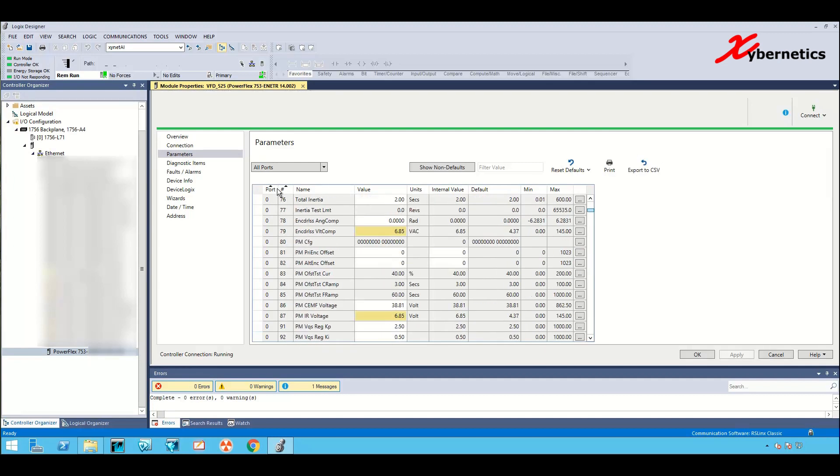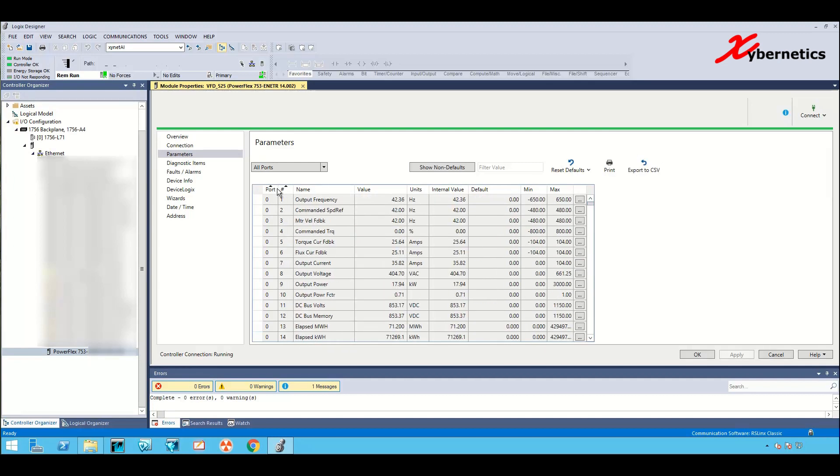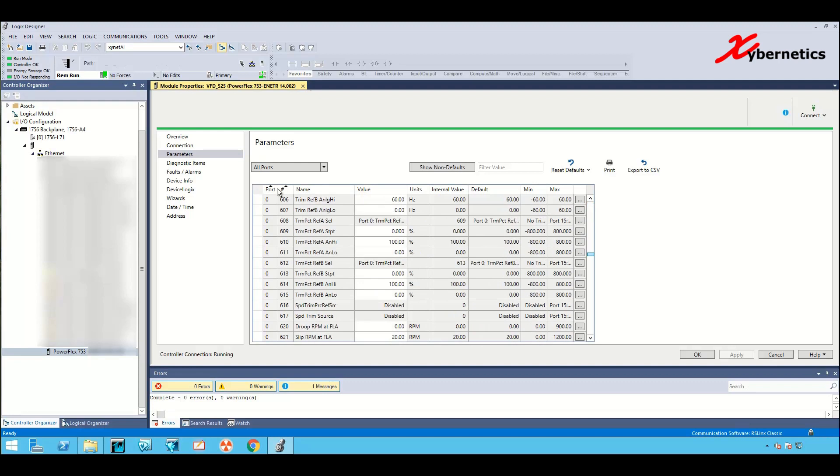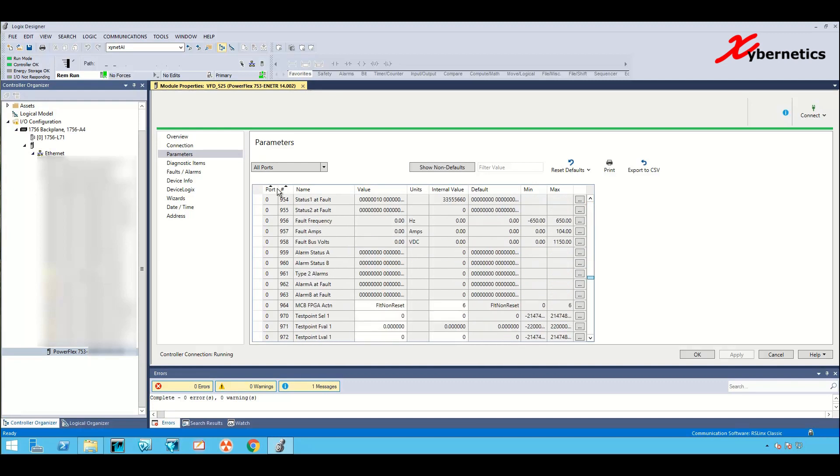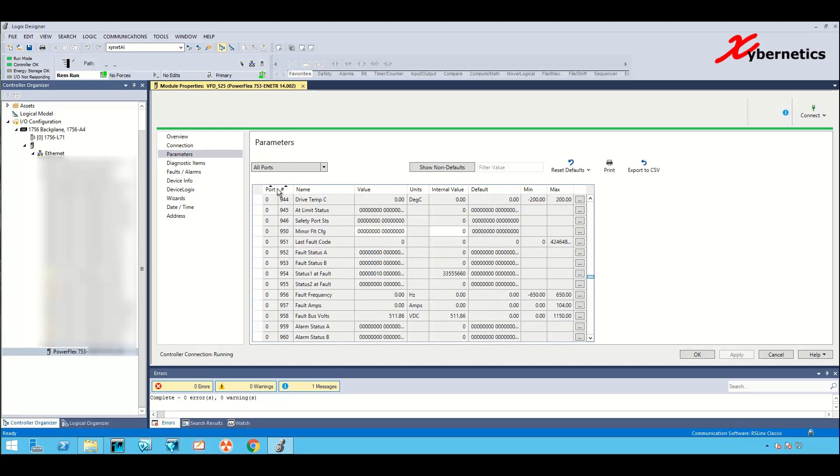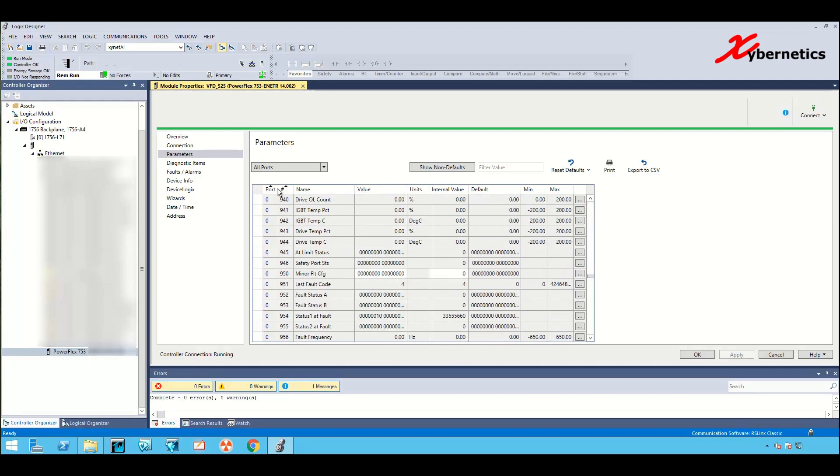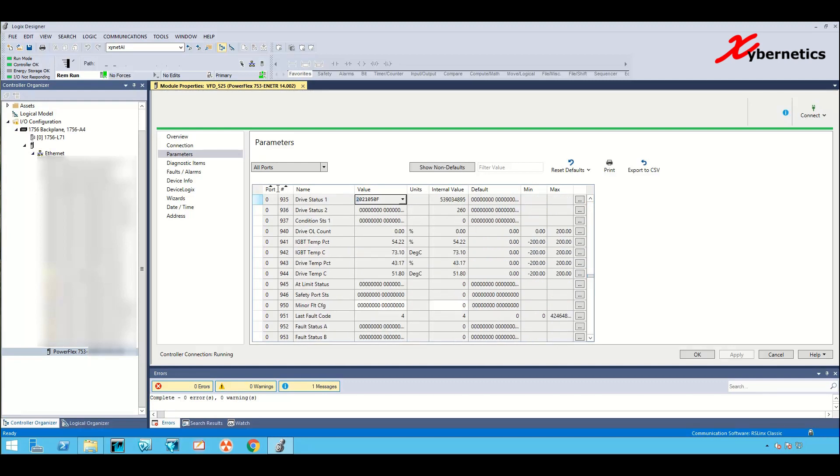Another way to tell that your VFD is running is by the output frequency which is showing us 42 right now. So I'm gonna get this VFD to stop and come back to parameter 935 here and keep monitoring it while the field guys stop the VFD.